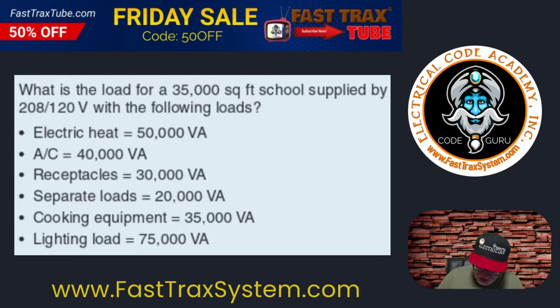So we're going to add all these up, remembering we're not going to include the AC because we get to use the larger. It says it clearly in 220.86, take the larger of the air conditioning versus the heating loads or space heating loads. So I'm going to do 50,000 plus 30,000 plus 20,000 plus 35,000 plus 75,000.